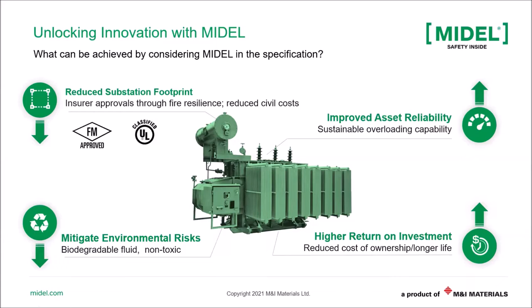So you can reduce the footprint of the substation, save money on not just land, but civil works as well. And then you've got improved asset reliability. Jinesh is going to walk you through some technical details on why you can extend the insulation system life of these transformers and get more bang for your buck. That relates directly to the higher return on investment, not just with the transformer in the substation, but with the entire substation operations and maintenance as well.